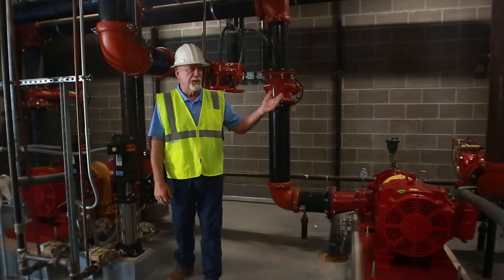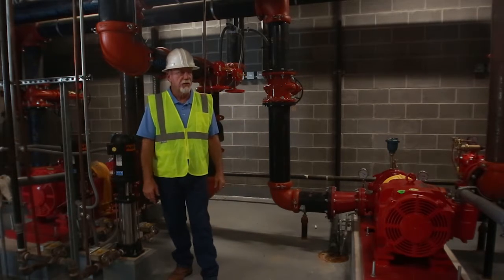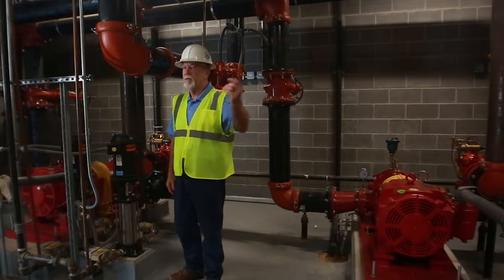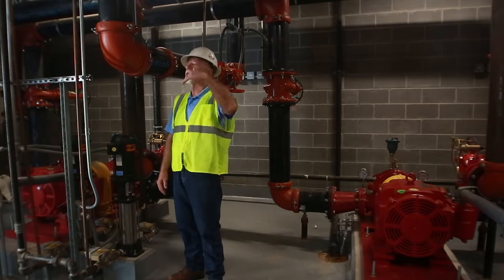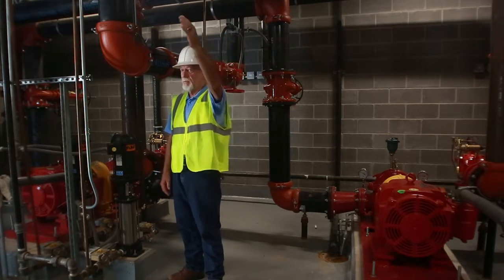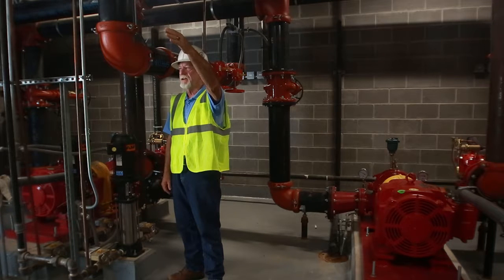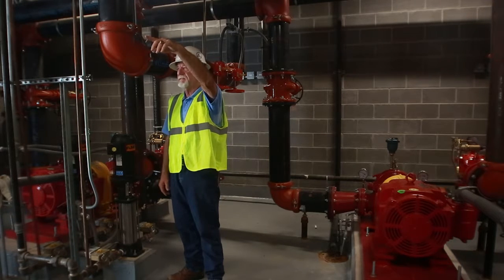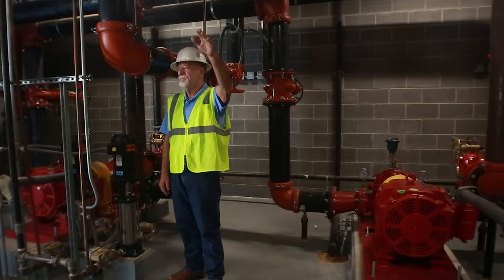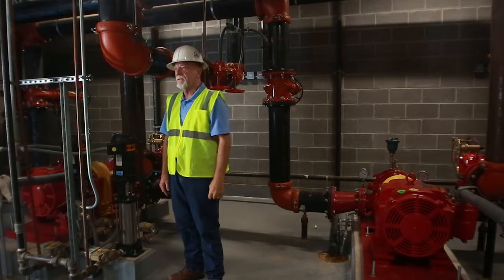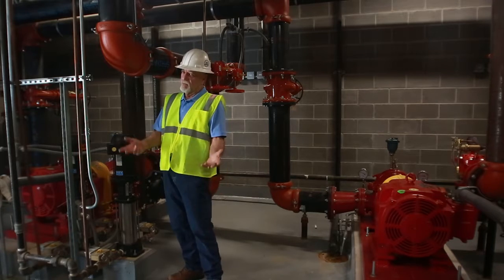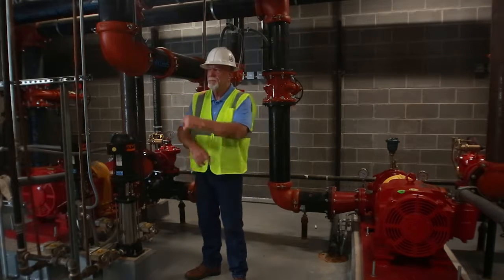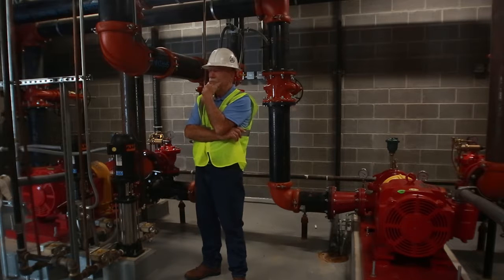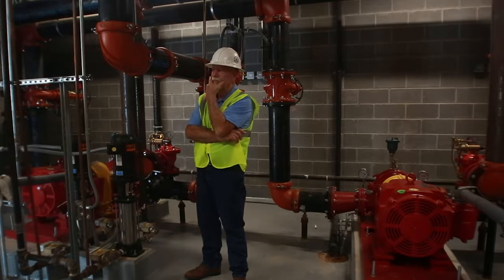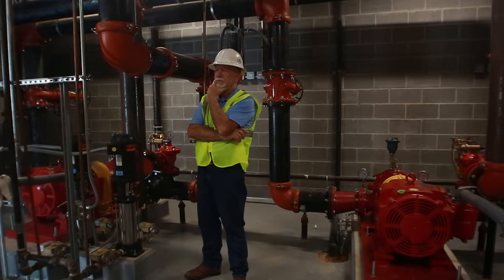Now, these are variable speed. I didn't even look, so I wasn't aware that these are variable speed controllers. That's a whole different animal than the conventional fire pump that you guys have in the other ones, I presume. I know the one in the other building is a conventional pump. Are the ones in the parking deck variable speed? Yeah. Okay, well, so you guys got the same cabinet and everything, just like these right here. Except for the secondary pump. Primary has this big one, just like I'm right here.